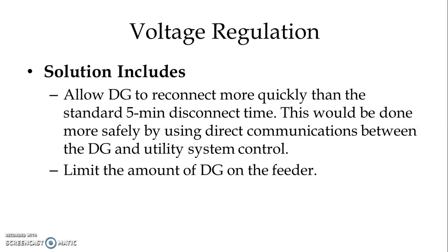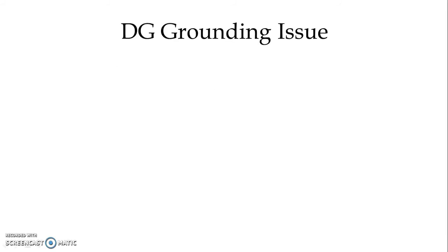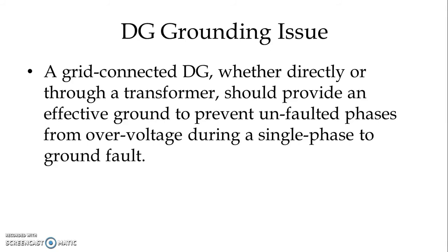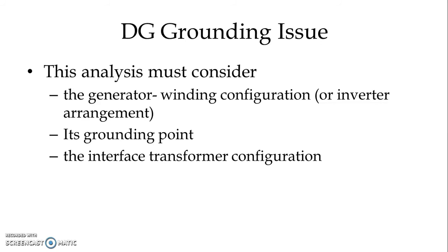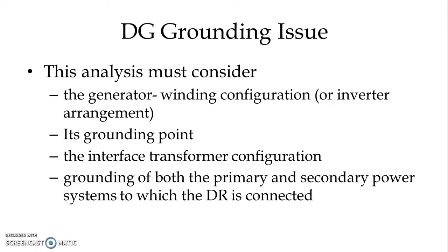Another solution is to limit the amount of DG on the feeder. We have another issue, and that is DG grounding. A grid-connected distributed generator, whether directly or through a transformer, should provide an effective ground to prevent unfaulted phases from overvoltage during a single-phase to ground fault. This analysis must consider the generator winding configuration or inverter arrangement and its grounding point, as well as the interface transformer configuration and grounding of both the primary and secondary power systems to which the distributed resource is connected.